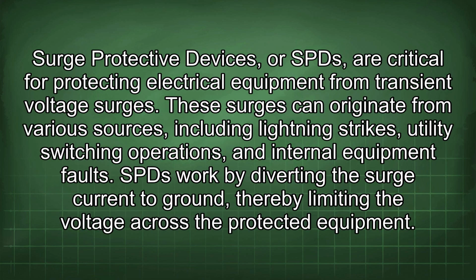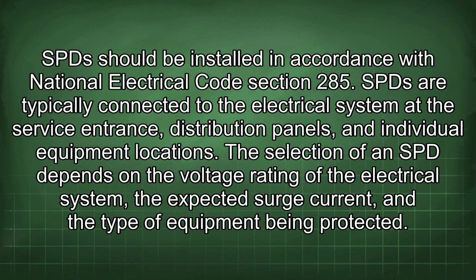Surge protective devices, or SPDs, are critical for protecting electrical equipment from transient voltage surges. These surges can originate from various sources, including lightning strikes, utility switching operations, and internal equipment faults. SPDs work by diverting the surge current to ground, thereby limiting the voltage across the protected equipment. SPDs should be installed in accordance with National Electrical Code Section 285.